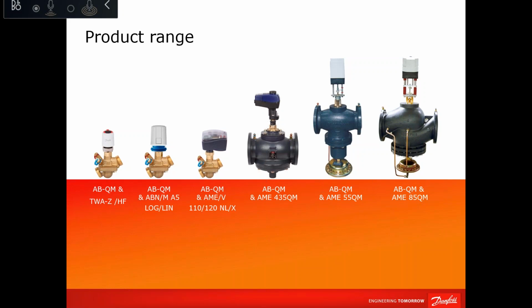If you go PICV with an on-off thermal actuator, then yes, you might save on the initial cost, but you will not be able to modulate, which means you will be wasting during the running cost. But some applications still use on-off, simply because it's a small number of units that does not really require modulation. We also have DN40 up to DN100, mainly used for air handling units, pressure handling units, and then DN125 up to DN250, mainly used in heat exchanger applications.